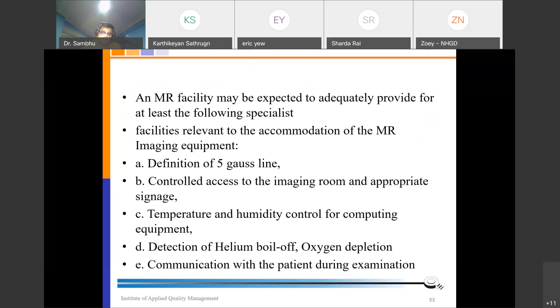Communication with the patient during examinations. You can talk to the patient, because when you are in the control room, how do you communicate with the patient? The patient can be communicated with easily. All equipment, including the patient transfer trolley in the MRI imaging facility, shall be MRI compatible. That you have to verify. The trolley or wheelchair which you are using for the patient must be MRI compatible.